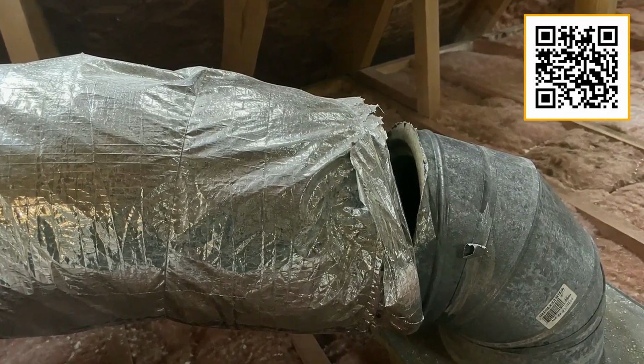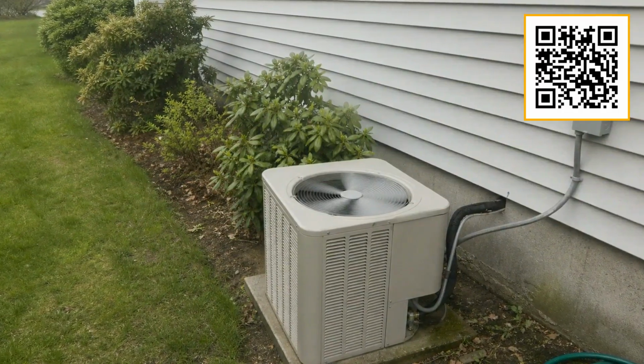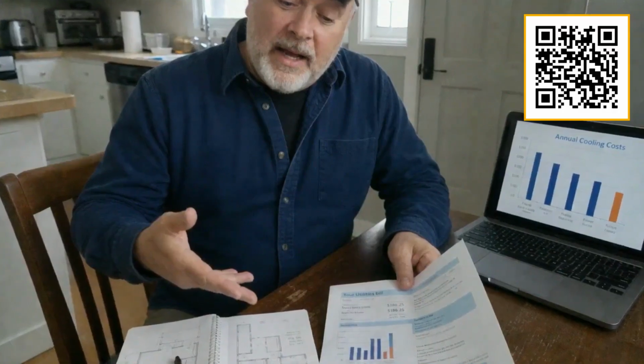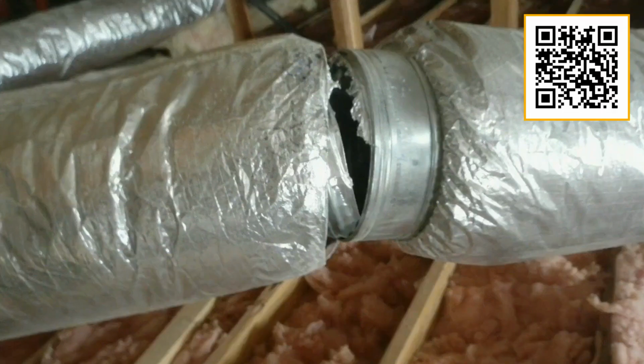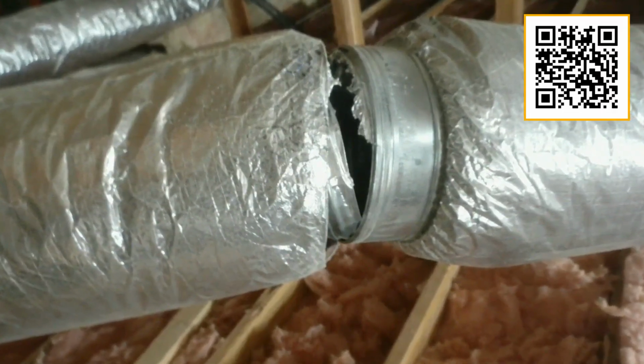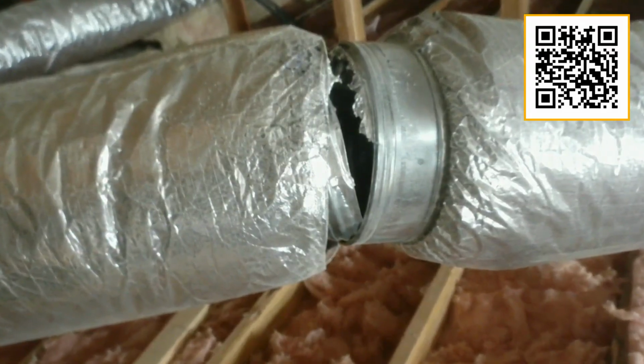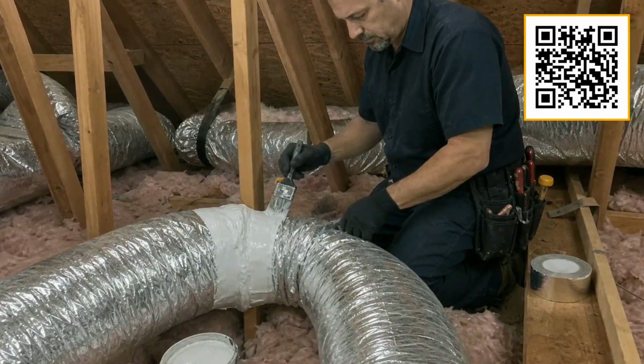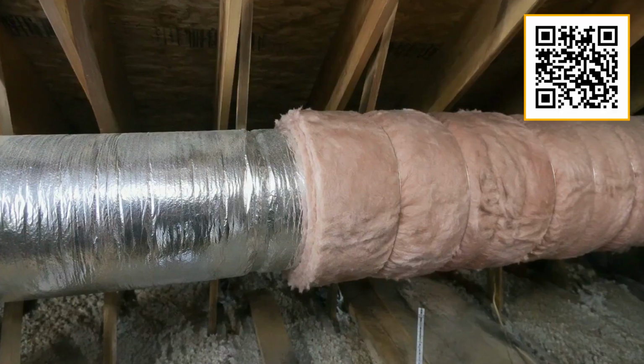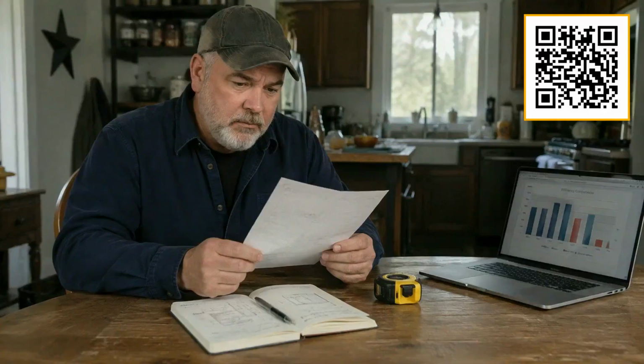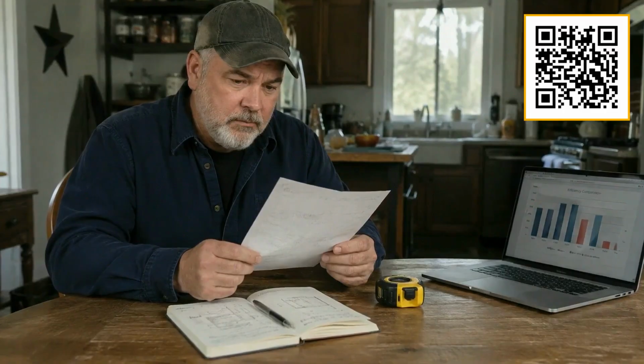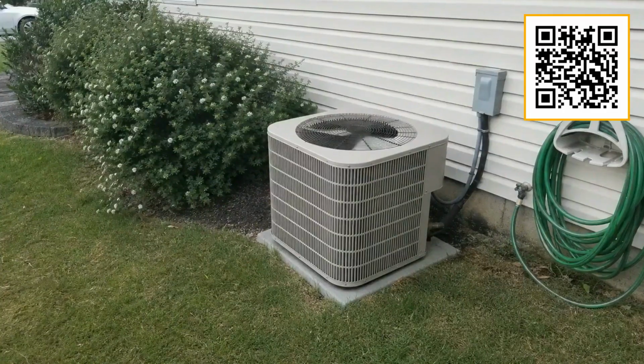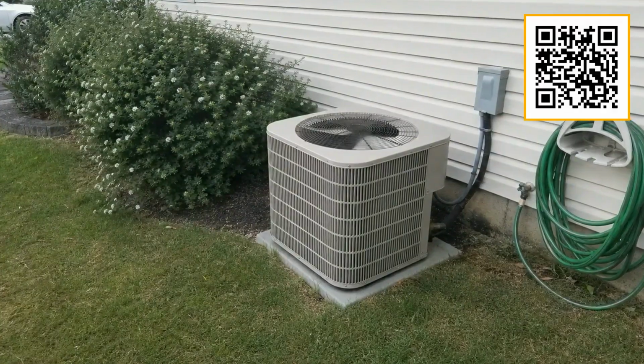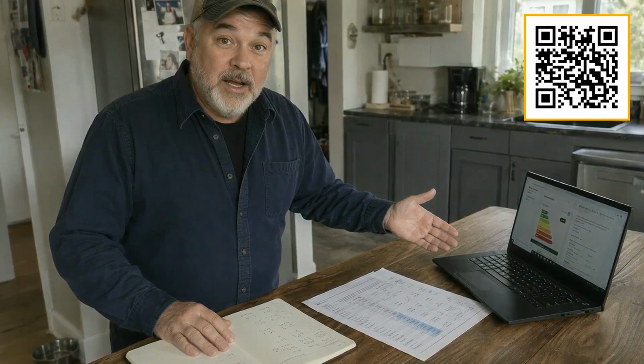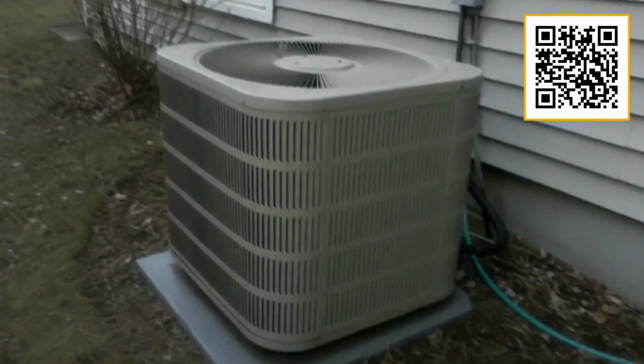The Department of Energy has published figures suggesting that duct leakage in a typical American home accounts for 20 to 30% of the energy used by a central HVAC system. If your annual cooling costs are running $1,200, you could be losing $240 to $360 of that straight through duct gaps into unconditioned space. A professional duct sealing job using mastic sealant or foil tape on accessible ductwork, combined with added insulation in the attic runs, might cost a homeowner $800 to $1,500 in labor and materials, and can pay for itself within 3 to 5 cooling seasons before a single dollar is spent on new equipment.